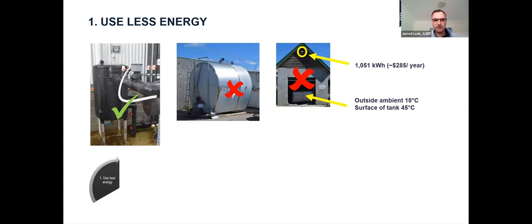If I can add to the insulation one there, Gab, if you're seeing condensation on those cold lines, on your lines with the glycol, all that condensation takes a lot of energy, so you're losing energy. And secondly, you're creating an environment for more mold and mildew that you may want to clean up later. So insulation, getting that over there, is really simple and easy to do. Usually about $5 to $10 a meter to install, and a payback of usually about 12 to 18 months on that one.